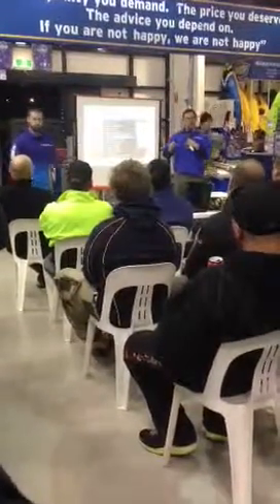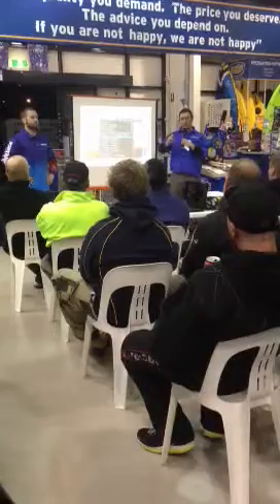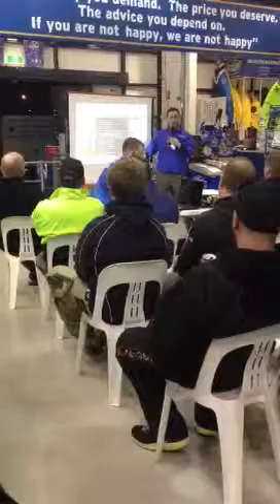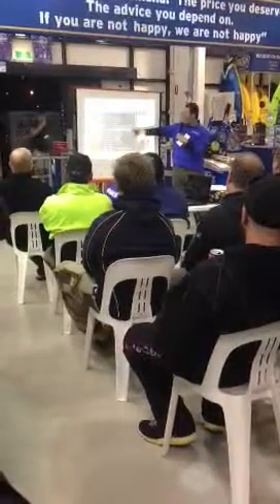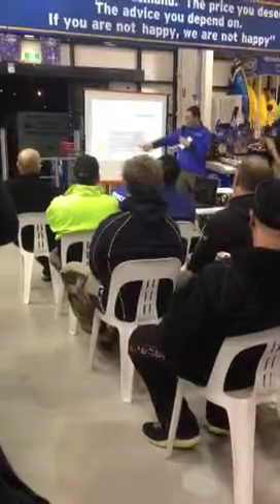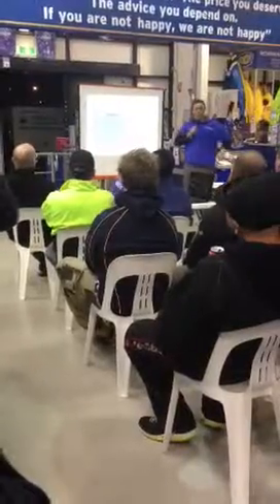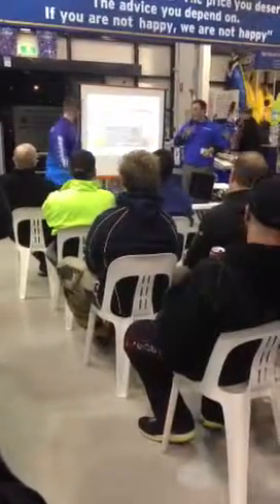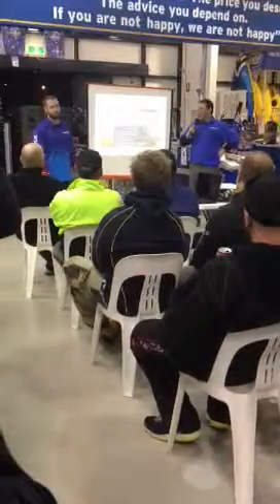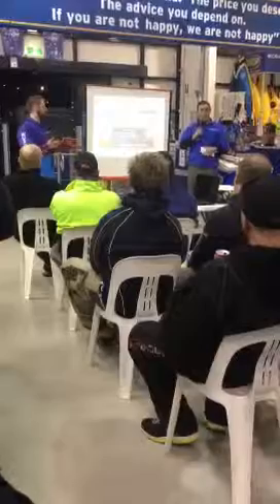On every transducer cable, just before it enters your screen, you'll have a silver tag on the cable, and that will tell you one of these numbers. From there, you just press enter, and that'll bring it up on your transducer type. Press save, and then you'll get the most out of your transducer. Without that, you'll probably be running your transducer at about 70%, but as you pair it, you'll get 100% out of the capabilities of the transducer.